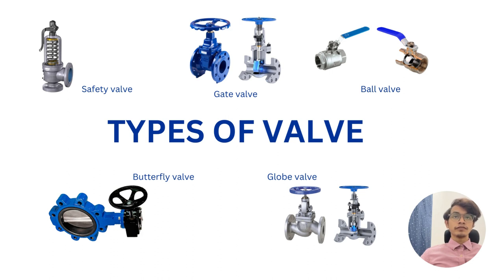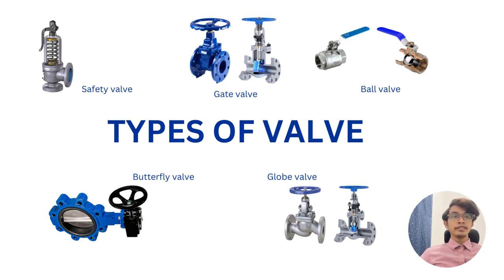Next is the butterfly valve. The butterfly valve is a rotary motion valve with a quarter turn, from 0 degrees to 90 degrees. When fully open, the disc is parallel to the piping and extends into the pipe. The main disadvantage of using a butterfly valve is its high pressure recovery, so its service is limited to low pressure drop applications.